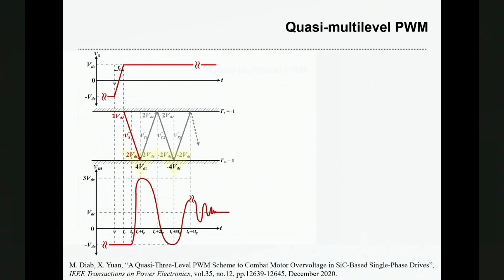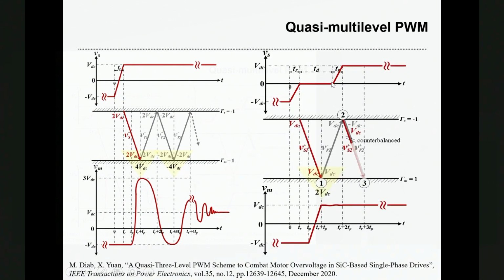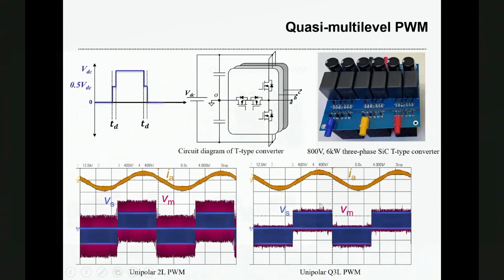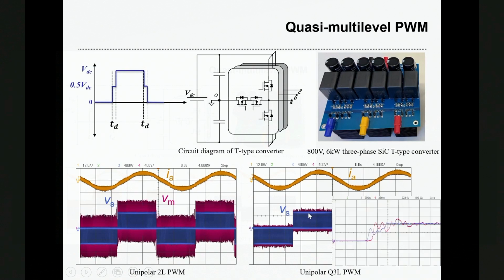There are other ways to reduce the over voltage. For example, we can use something called quasi multi-level PWM, where this is the standard switching edge. If you insert a short time duration here, creating a third level, it can help to eliminate or cancel the reflected wave. Then you can remove the voltage overshoot at the motor terminal. Here I show you the experimental results where if you use a quasi 3-level PWM, you can remove the voltage overshoot at the motor terminal.